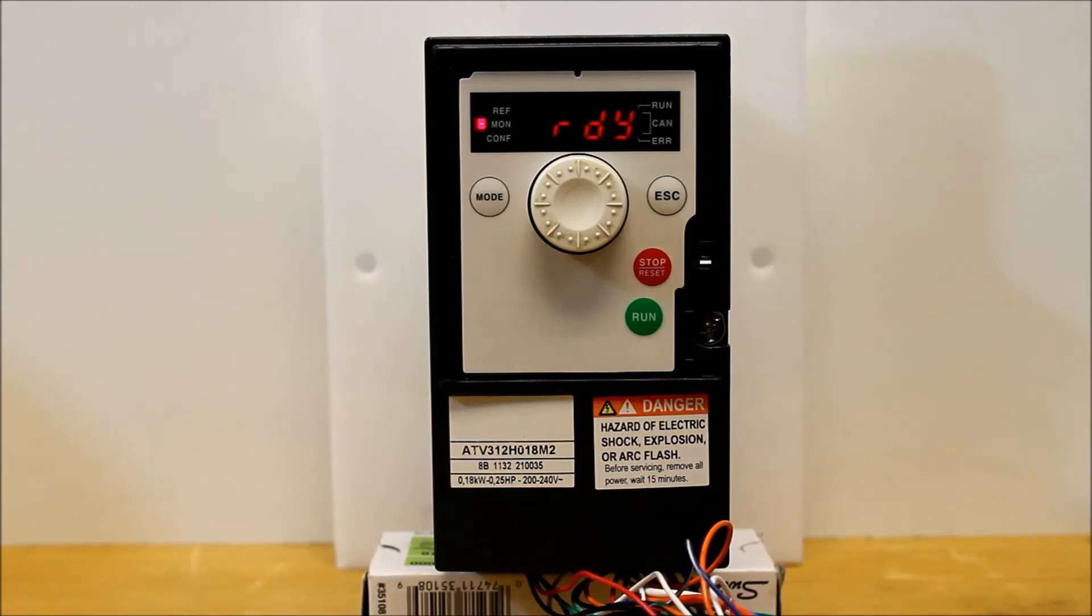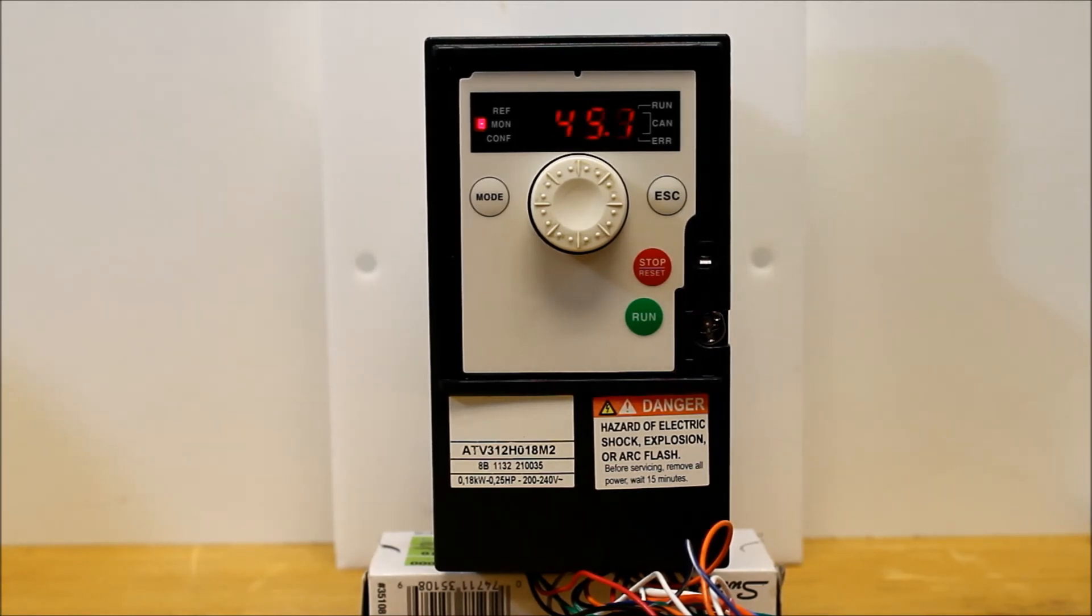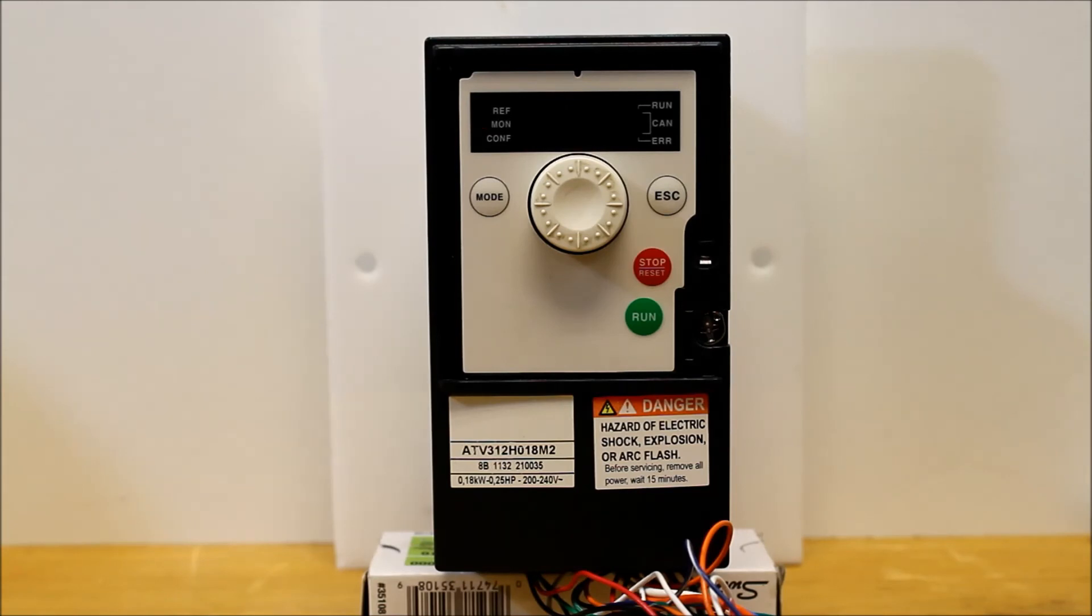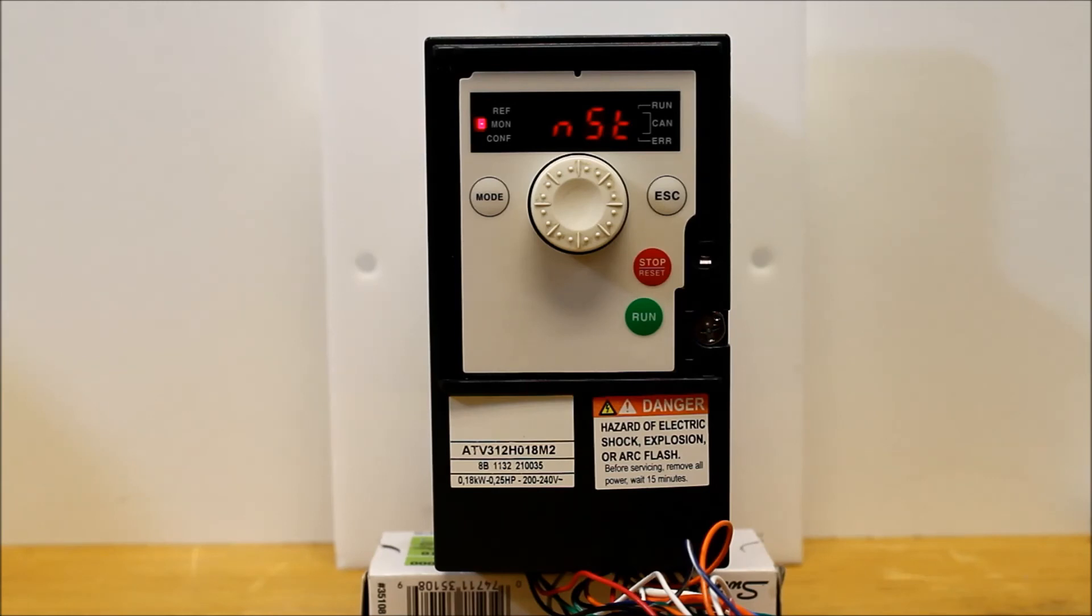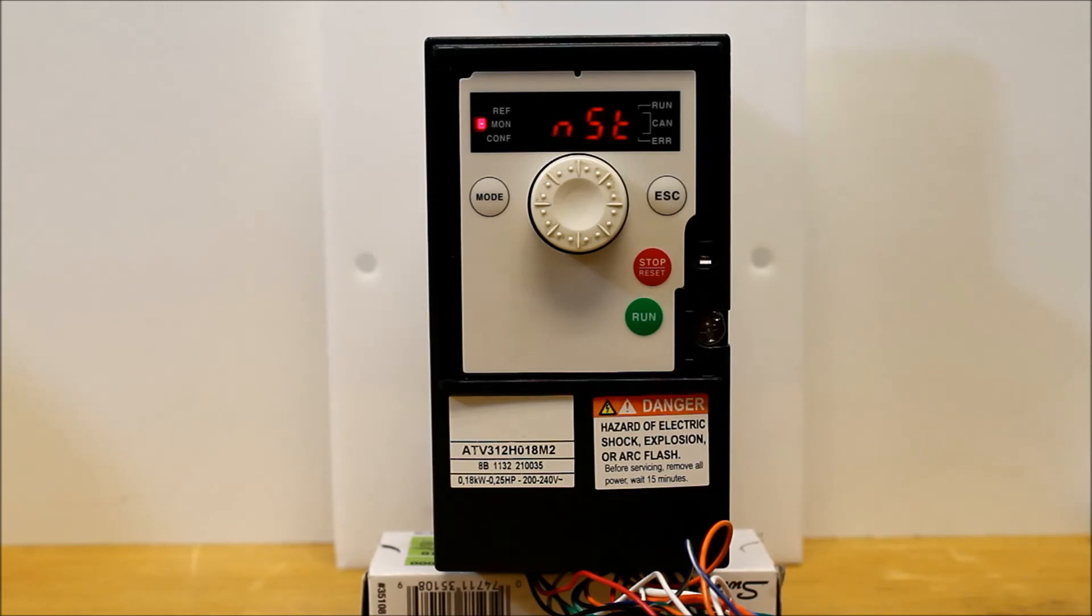But let's go ahead and enable the run command. Kill power to the drive. Let it go blank. And then power back up. And you get an NST. As you can tell, with the run command enabled upon power up with a transition state, it did not like that. It expected the drive to get power first, and then you toggle the run command.